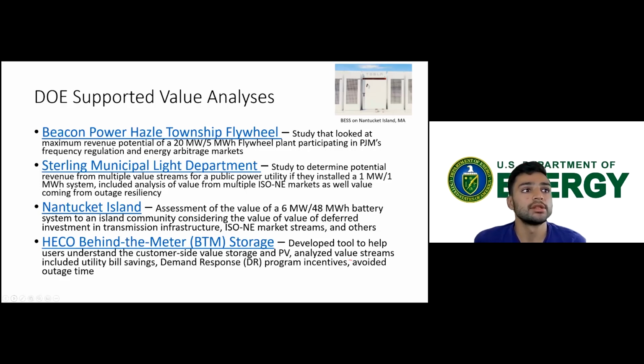Moving on, the Nantucket Island study was carried out by Pacific Northwest National Lab. This is a really interesting case for island communities connected to a mainland grid, and an example of how storage can allow for a resilient and economic solution for communities across the world in a similar situation. Nantucket Island, off the coast of Massachusetts, receives most of its power from two submarine cables connected to the mainland grid. The report compared the value of adding a battery system versus investing in another undersea cable to ensure adequate supply during a contingency event where one of the existing cables would go offline during a period of peak demand, in this case during the summertime.